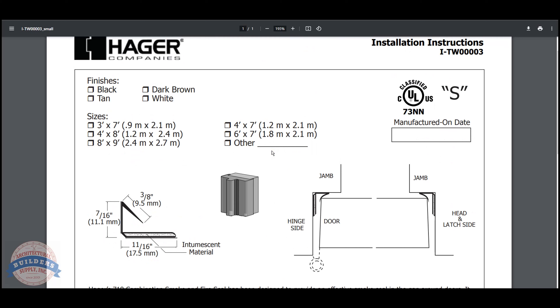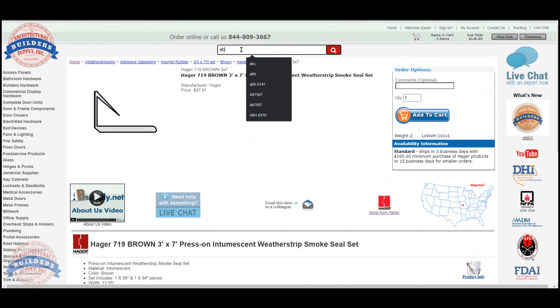Something very important: NFPA 80 tells us very clearly what the door gaps are. The tech support individual stated that if you submit this to the AHJ — the authority having jurisdiction, the fire marshal — and they accept it, then it's acceptable. Per standard, if NFPA 80 was adopted into your local code, the standard becomes code. However, the inspector supersedes all written documentation. If they approve it, then it is agreeable.